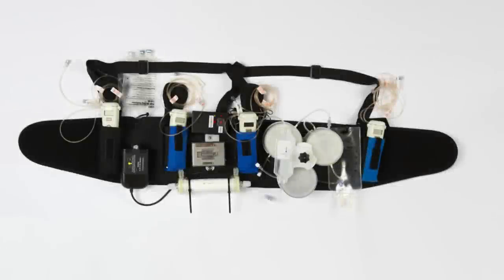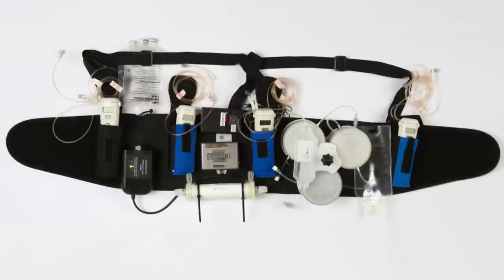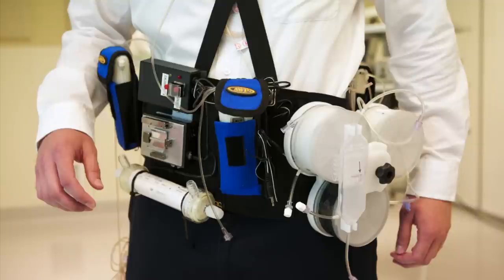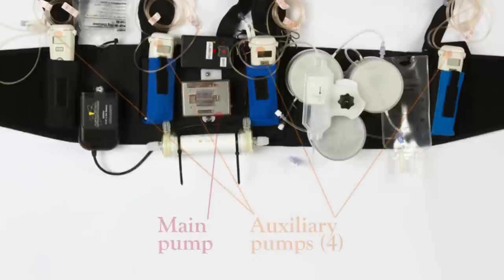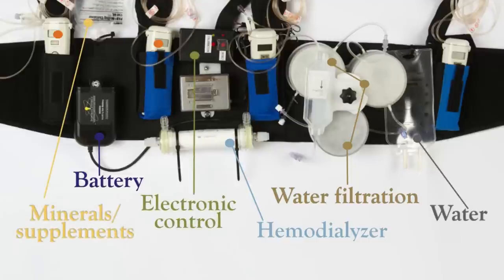When one looks at it, one sees all the different components of a dialysis circuit, but they're just much smaller and they've been designed ergonomically so that they're wearable and they weigh 9 or 10 pounds instead of 80 or 90 pounds. There are some really novel technologies being deployed, particularly a very innovative pump design, and that's one of the smallest components of the entire circuit. Much of it is really fundamentally not tremendously different than dialysis today, but just with improved technology.